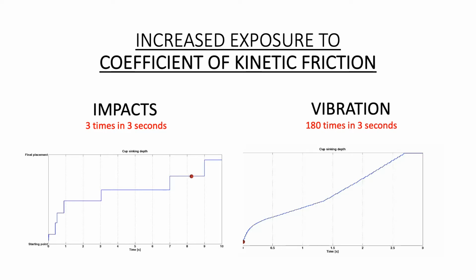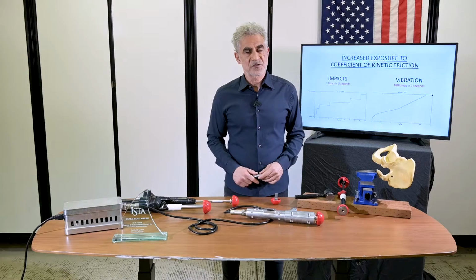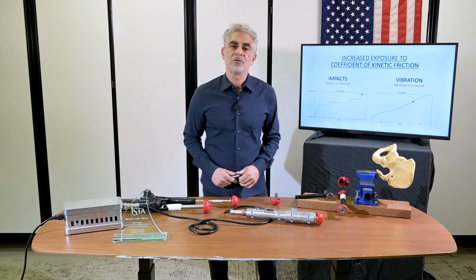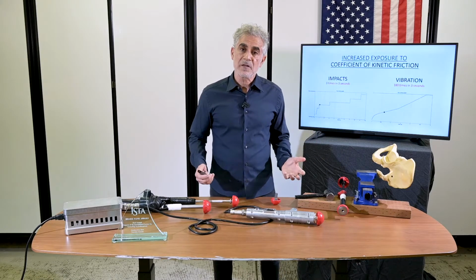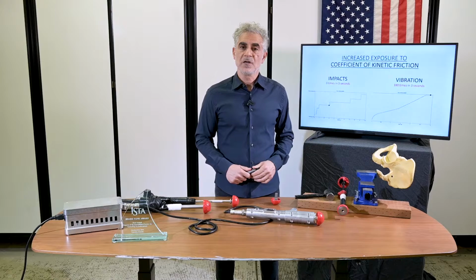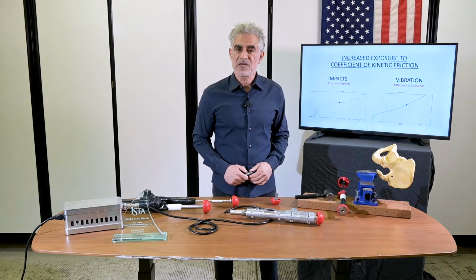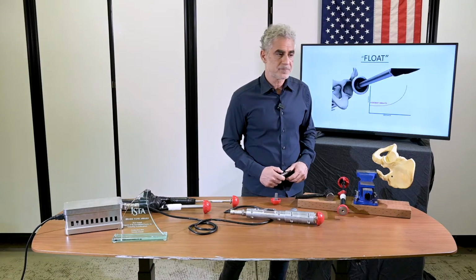300 newtons of force, which is less than 1/10 the amount of force typically required using standard technique with a mallet. I believe this could be attributed to the frictional phenomena at the interface. When the implant is vibrating at higher frequencies, it has a higher exposure to a coefficient of kinetic friction, which is lower than the coefficient of static friction by as much as 30 to 50%. This may mean that the resistive force to insertion is lower by 30 to 50% with vibratory insertion technique.